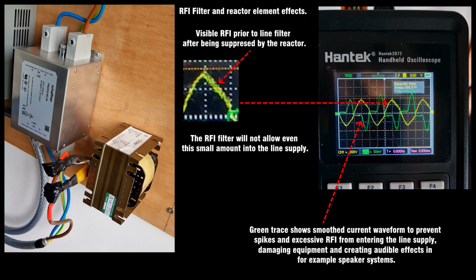Prior to anything in the system, these two items will be installed. They will prevent any items being damaged on your line supply and the surrounding area's line supply. Without them, you will have essentially accidentally created an EMP-like weapon, which can stop devices like Wi-Fi and satellite systems from working properly. That is simply because a variable frequency drive is inherently a very noisy device. Switching thousands of times a second can generate a lot of RFI on the line supply. The reactor also has another use in the system, as it can smooth the current waveform, preventing big load spikes that can take out light bulbs and other similar devices.